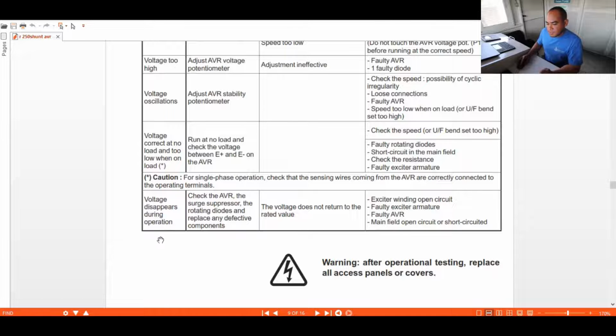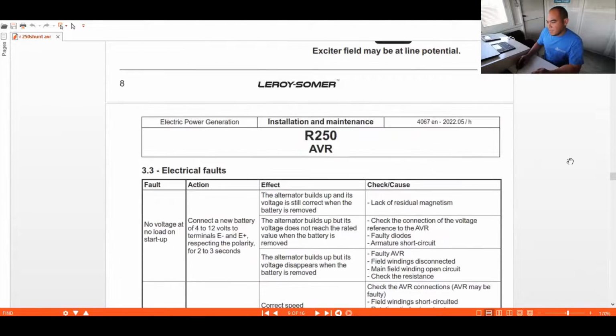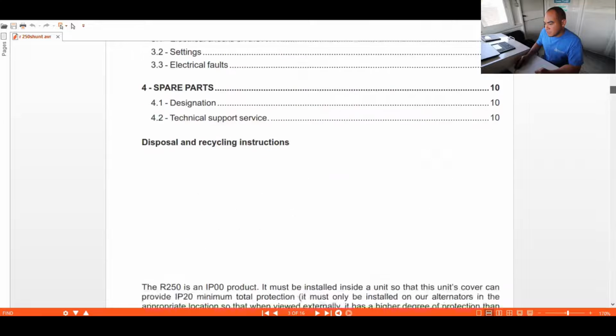So here also, the voltage disappears during operation, same as here. Check the AVR source of excitation, rotating diode, and replace the defective components. It is almost the same, there's no difference. So exciter winding is open, faulty exciter armature, faulty AVR, main open circuits. These are the common things you have to check if you are encountering this kind of problem. So you have to troubleshoot it this way. Check everything as I mentioned here to find and fix the problem. So that's all that we have here, that is the importance of this kind of AVR.